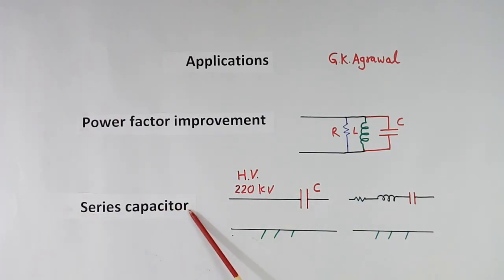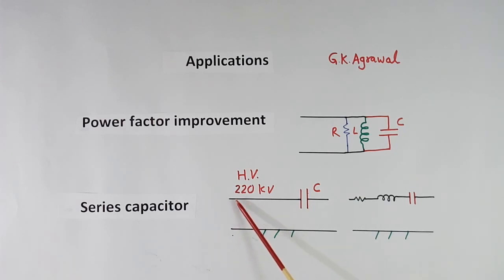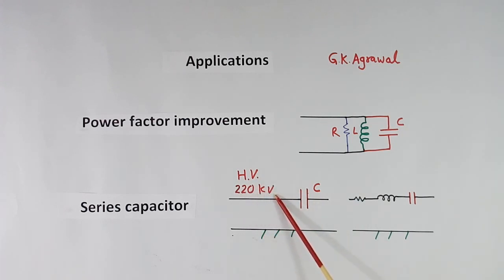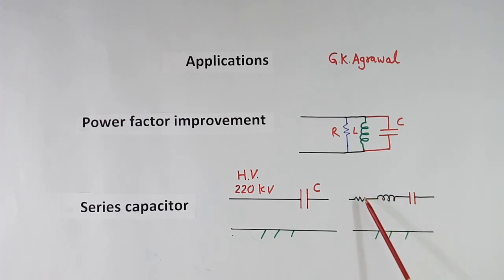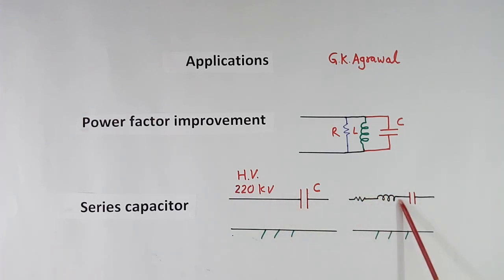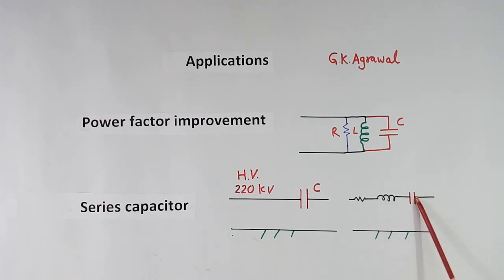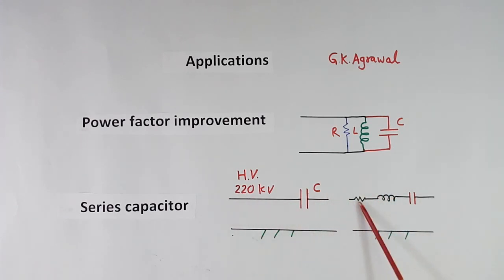Another application is series capacitor, also called series compensator. Power transmission is done using high voltage lines — maybe 220 KV, 3 phase. Now this wire will have resistance and inductance — this R and L are the values of the wire itself, not connected extra. Because of this inductance, transmission capacity of this transmission line comes down. To improve that, we connect a capacitor in series. This capacitor will cancel out this inductance, and power transmission capacity of this transmission line will improve.